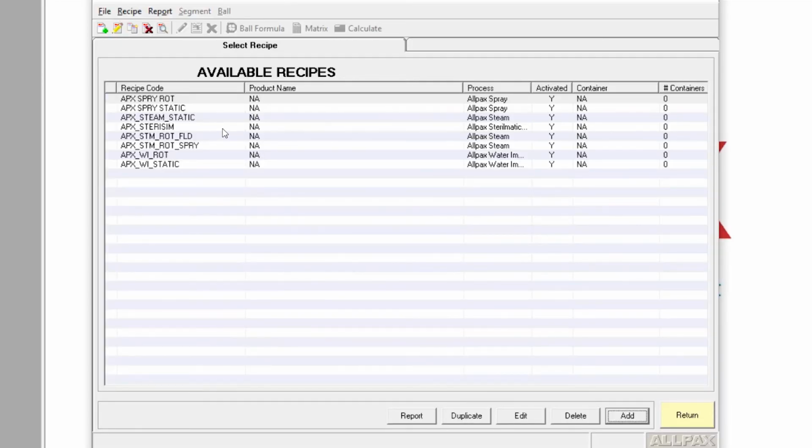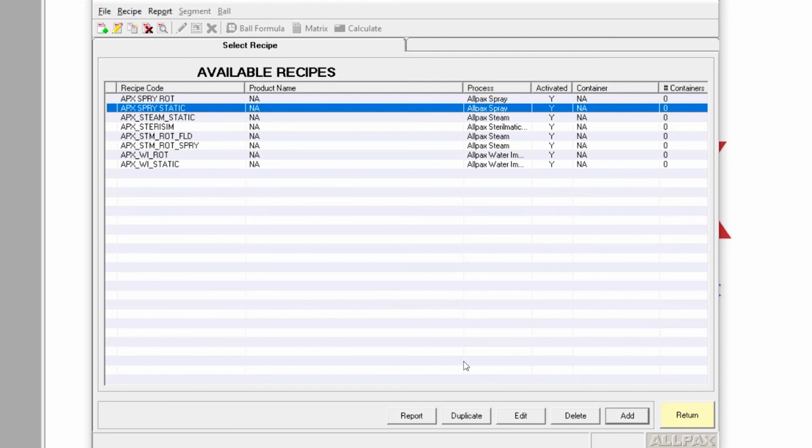If it detects the drop. Right, if it detects the drop. If there's no drop in your process, it'll skip the alternate cook entirely. Okay, and you can set how long the alternate cook is. Right, or if you wanted to save this product at any cost, you could have 10 alternate cooks. Like, if it drops all the way to 230, I need to go 30 minutes, something like that. So now that we have a recipe, we can either duplicate the recipe or delete the recipe.